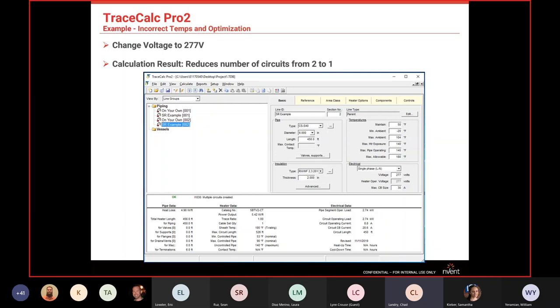Power distribution and labor are where most of the cost is in heat tracing. Minimizing circuits is critical to saving customer money. Sometimes your hands are tied by plant specs calling for certain voltages, but if you're starting a new design with a new transformer and panel, you can sometimes influence the customer to optimize voltage if you can show cost savings.